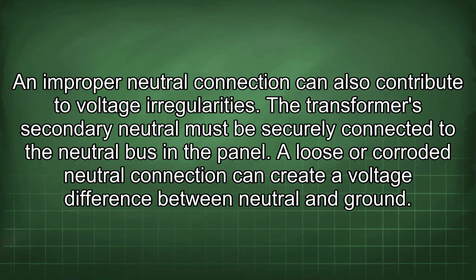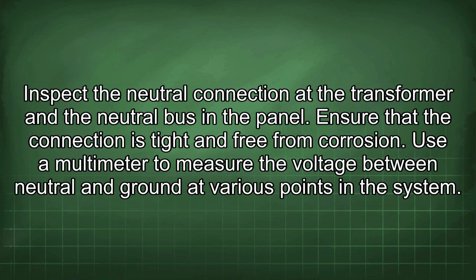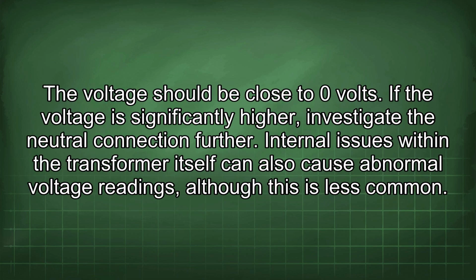An improper neutral connection can also contribute to voltage irregularities. The transformer's secondary neutral must be securely connected to the neutral bus in the panel. A loose or corroded neutral connection can create a voltage difference between neutral and ground. Inspect the neutral connection at the transformer and the neutral bus in the panel. Ensure that the connection is tight and free from corrosion. Use a multimeter to measure the voltage between neutral and ground at various points in the system. The voltage should be close to 0 volts. If the voltage is significantly higher, investigate the neutral connection further.